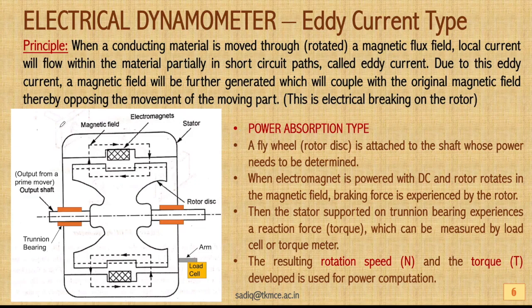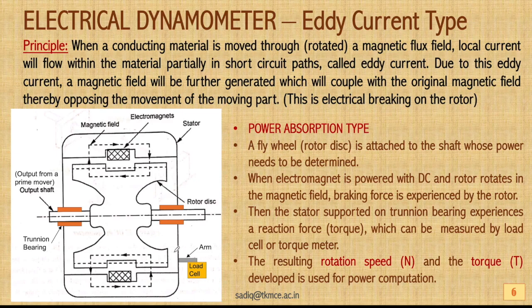In the eddy current dynamometer construction, there is an output shaft and a rotor disc with teeth, typically made of mild steel or copper. In the stator there are windings that act as electromagnets. The stator casing is supported on trunnion bearings. An arm connected to the casing is linked with a load cell, so any reaction developed in the casing is transferred to the load cell.